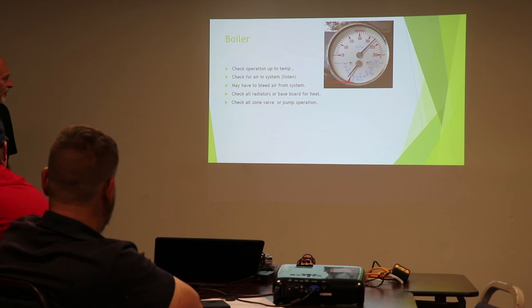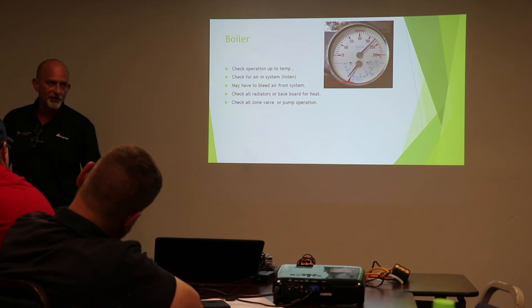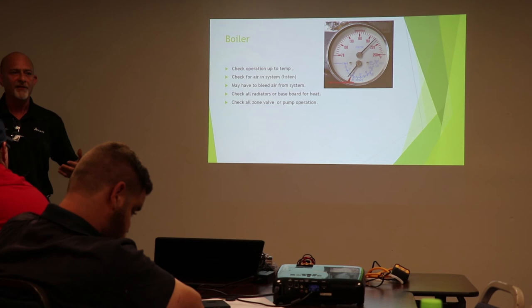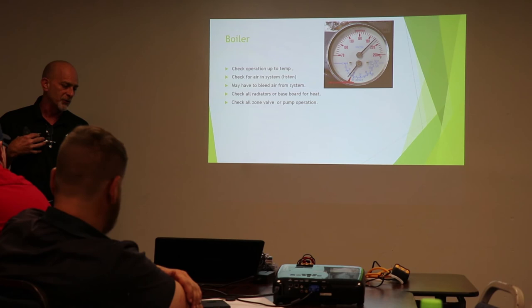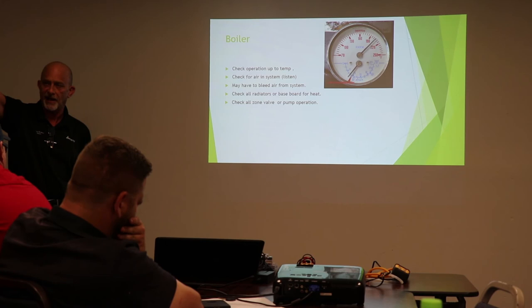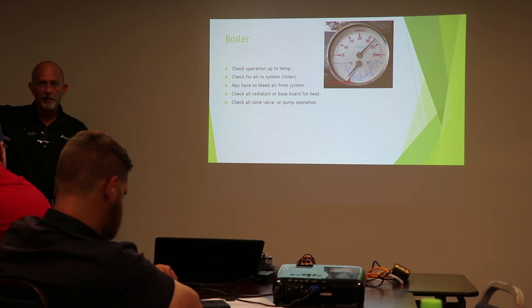We also want to check all of our zone valves and or pumps. Every house is different. You may zone with pumps, you may zone with valves. You might have some type of zone valve control or pump control on the wall. Personally, when I do installs, I like a nice clean install. I've got a control on the wall, stat, stat, stat, control, valve, valve, valve, or pump, pump, pump. My zone board tells me which zone is calling, that turns your boiler on. It's just a clean install. Adds a little bit to a job, but looks a lot nicer.